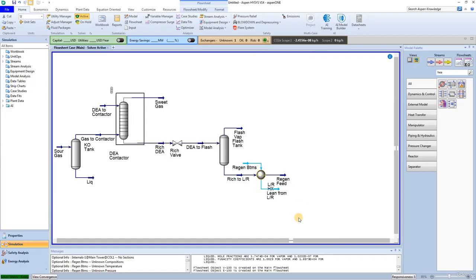The amine regenerator is modeled as a distillation column. There are 20 real stages, 18 stages in the column section, plus a reboiler and a condenser, just as you did on the DEA contactor column. You will provide tray information which will allow the acid gas package to calculate efficiencies for the acid gas components H2S and CO2. The regenerator will also incorporate an adaptive damping factor.